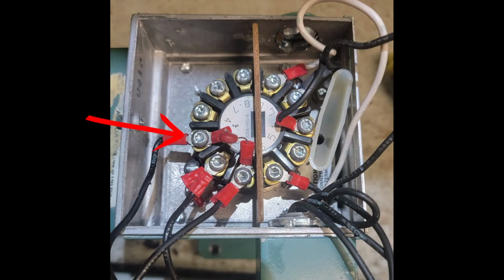Either way, paying attention to this wiring is going to be one of the major things that's going to mess you up. So more than just having your open and close power wires, you've also got the relay up here that is going to identify when the actuator moves into a full closed position, because there's an internal switch in here that gets triggered once it hits its full rotation one way or the other. And we have to make sure that when we swing into the fully closed position, that relay sends a signal back to the control board so it can verify full closed position.